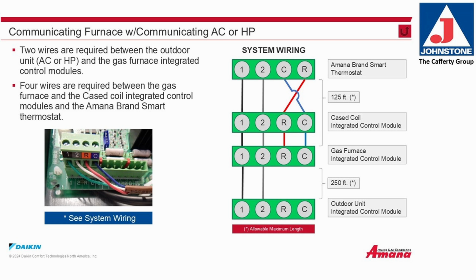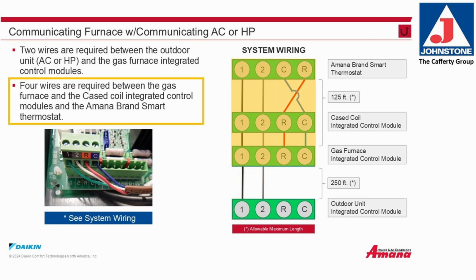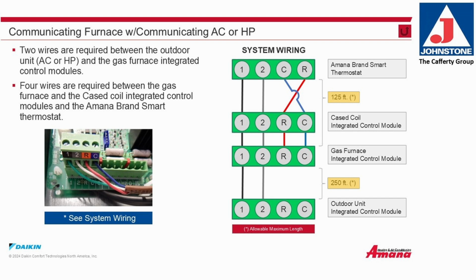Communicating furnace combined with a communicating AC or heat pump. 2 wires are required between the outdoor unit, AC or heat pump, and the gas furnace integrated control module. 4 wires are required between the gas furnace, the cased coil integrated control module, and the Amana brand smart thermostat.